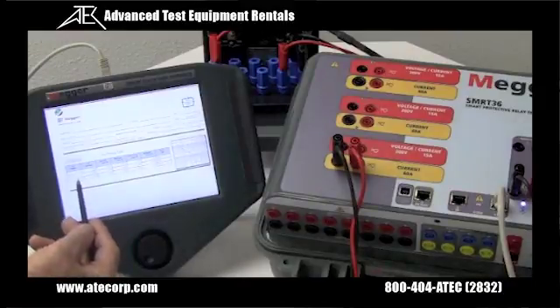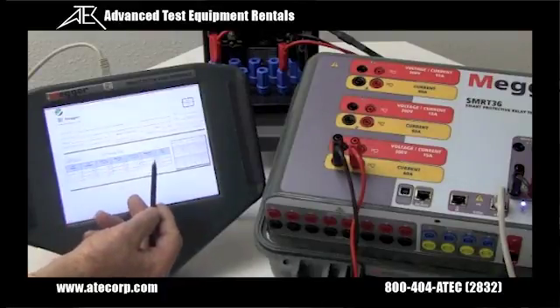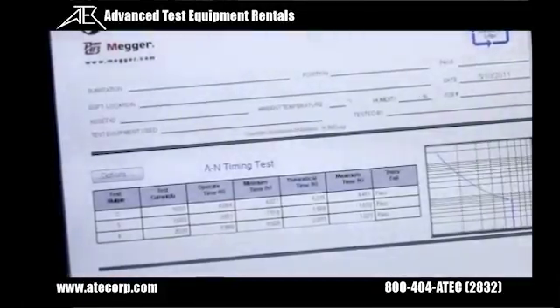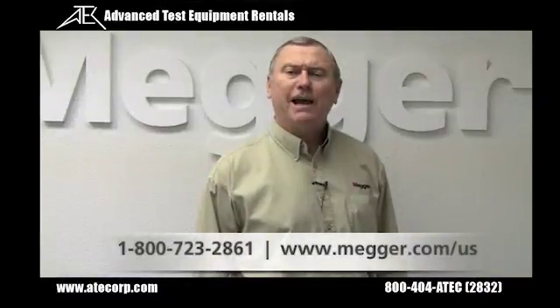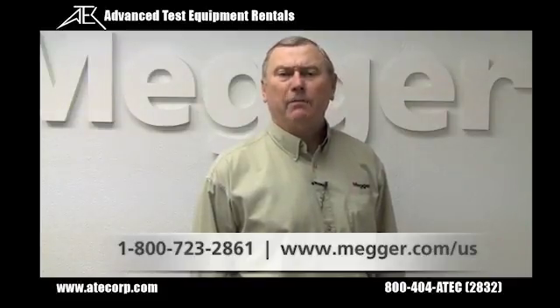Here we can see the results for our timing test at two, three, and four times tap — showing the test current, trip time, theoretical, min, max, and whether it passed. It passed all points, and we see the three test points on the curve. Thank you for your time; should you have any questions, please contact your local Megger sales rep.